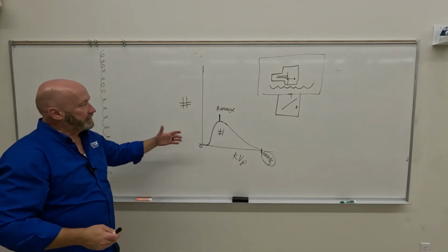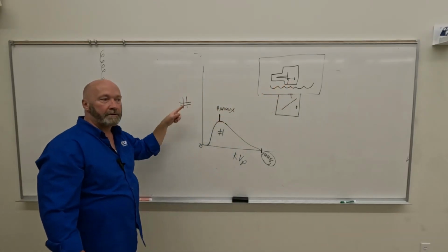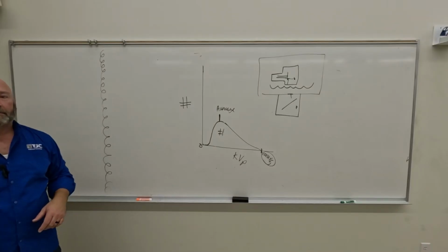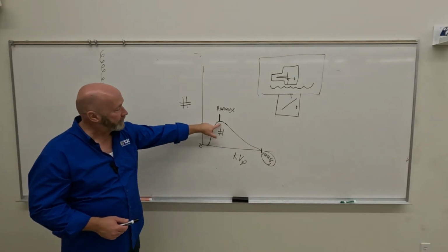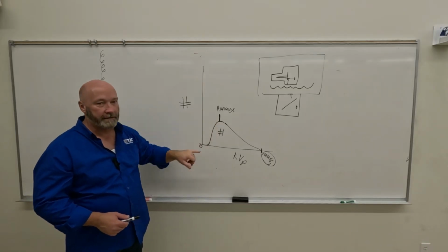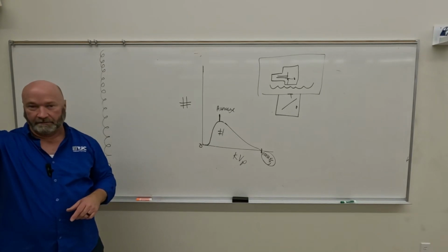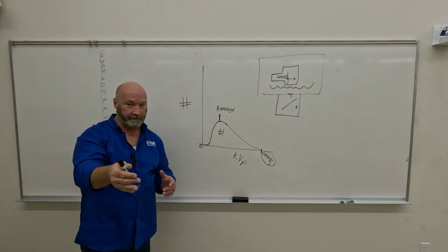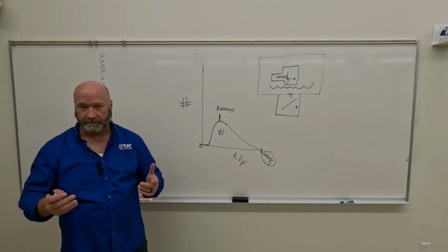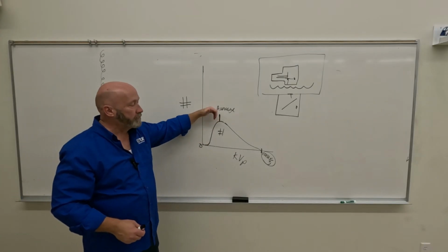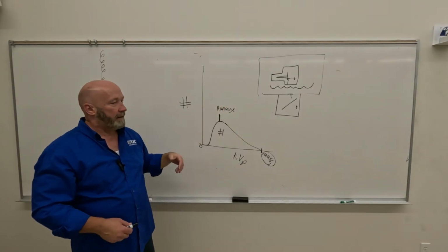As you know, whenever we had the X-ray beam at the target, we had much more lower energy X-ray photons. So what happens to our average as we increase filtration? If the height of this thing represents our average, and we got rid of all those low energy X-ray photons, what happened to our average? The average gets higher. The average beam energy. I didn't make myself completely clear: the average X-ray photon energy, to dial it in a little tighter, increases with increased filtration. We're going to draw that out again on Wednesday.